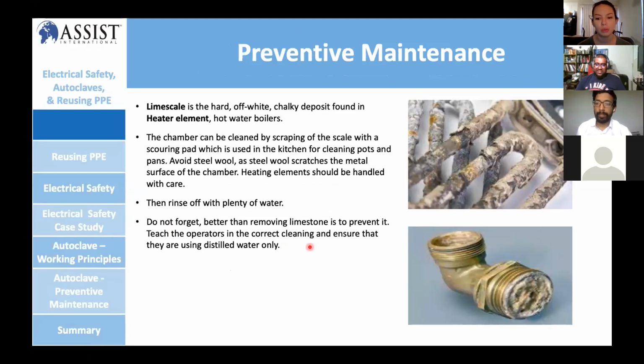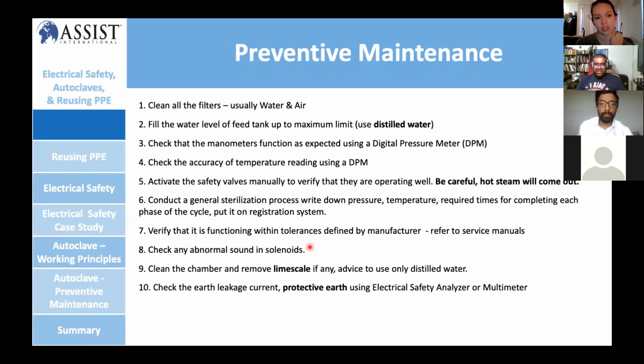Guna, how often should people be doing preventive maintenance and cleaning limescale off of their autoclaves? If you use distilled water, normally you don't get limescale, but if not, you have to do it about every 3 months. Make sure the heating element doesn't have any leak. Make sure you clean the surface properly. That's an important thing. That makes sense.